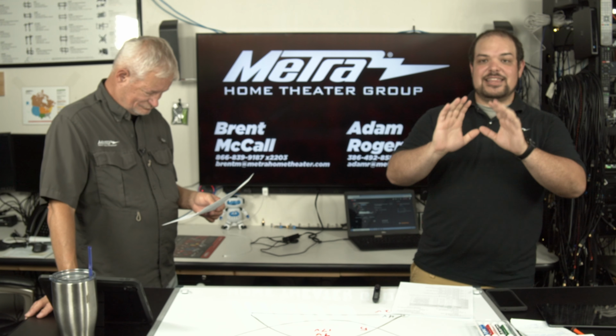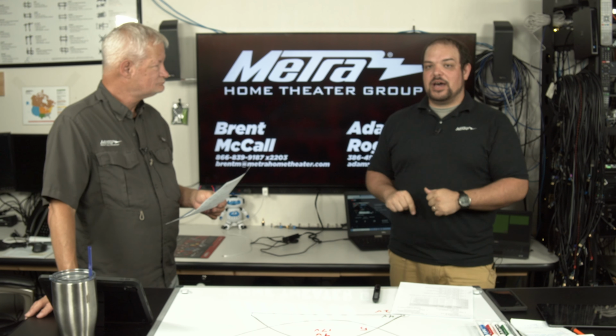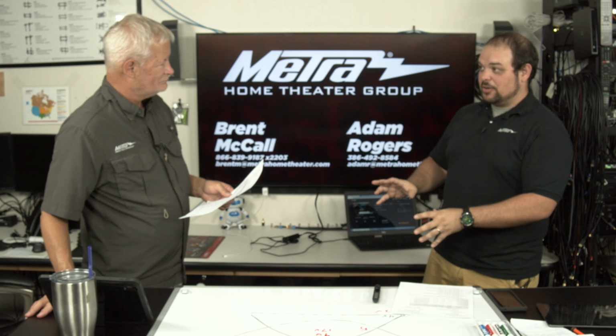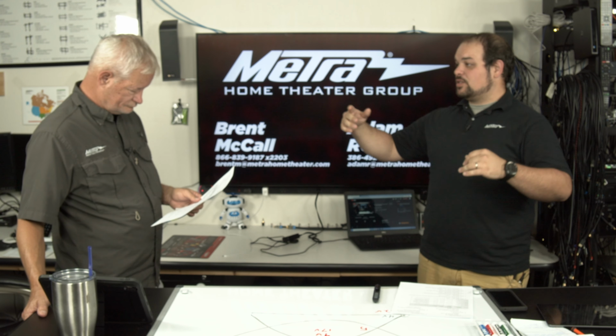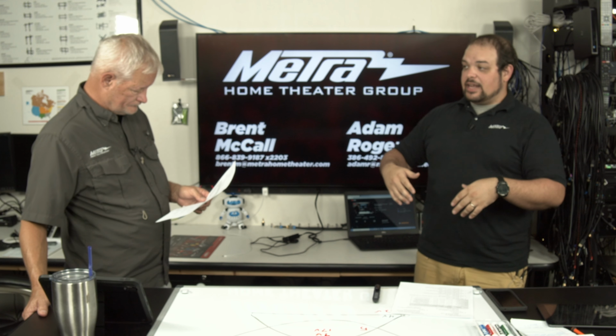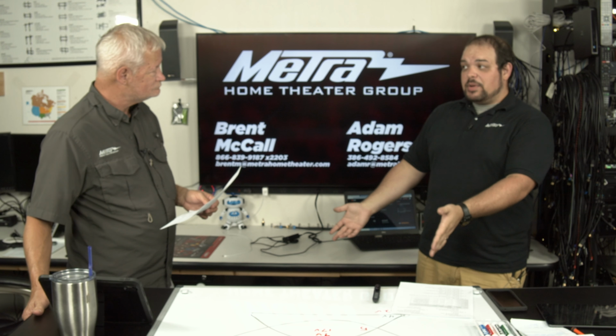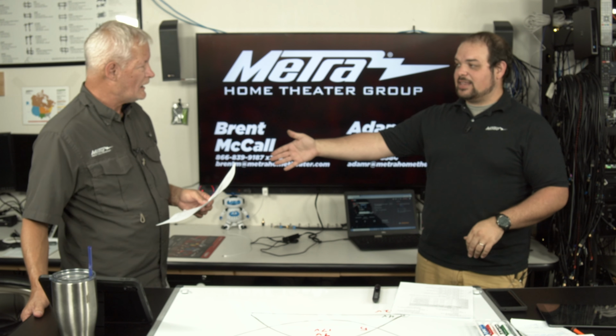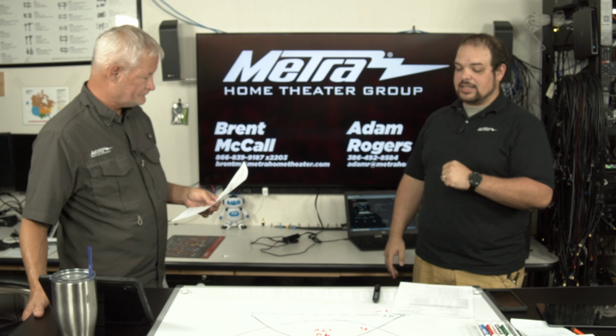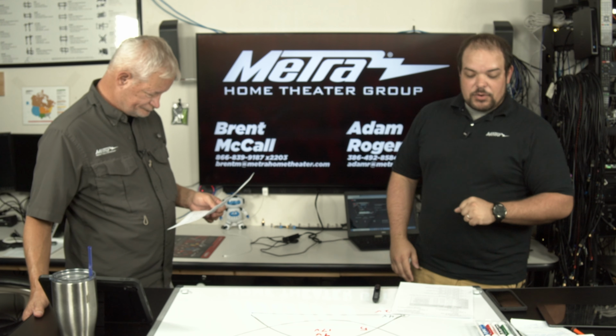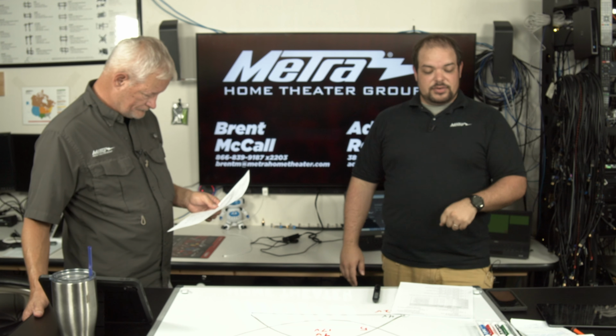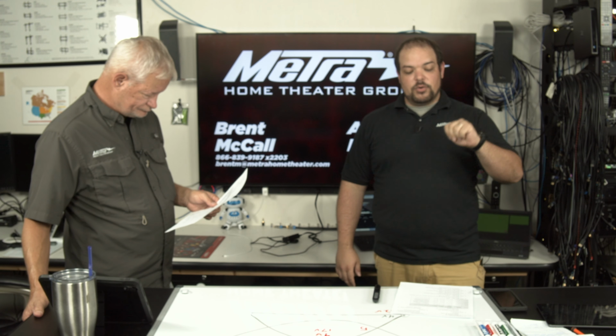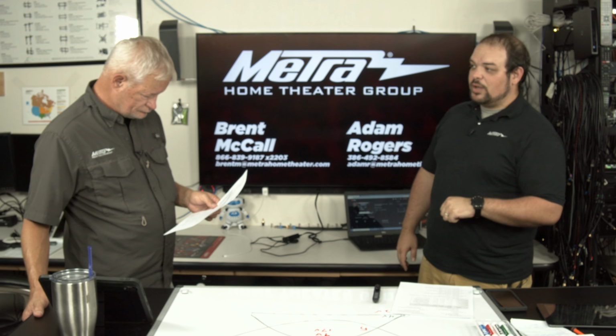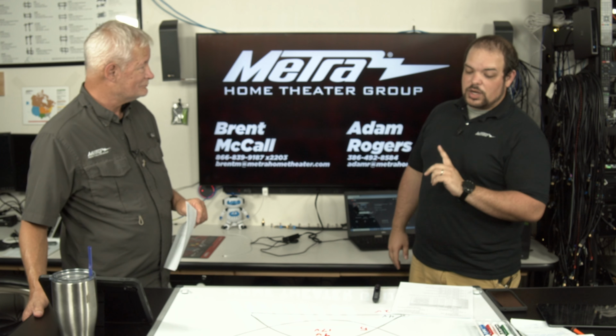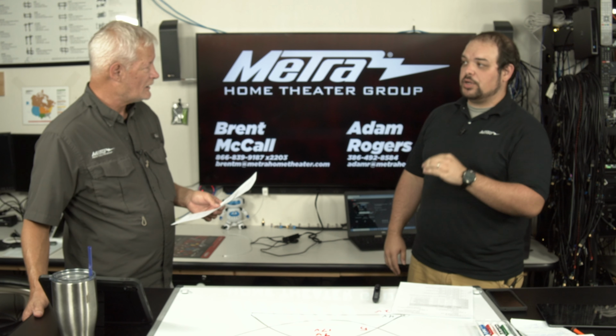So at this level, at 51 watts at the powered device, that's a lot of power. Because if you then convert that back over to, say, 12 volts, and then you do the math on that, you've got quite a bit of amperage to work with at the end of that line. And it's the amperage that runs stuff. Exactly. So that's 51 watts, and then of course it's 60 watts at the output. And then Type 4 is 71.3 watts at the device, with a full 100 watts maximum output at the PSE.